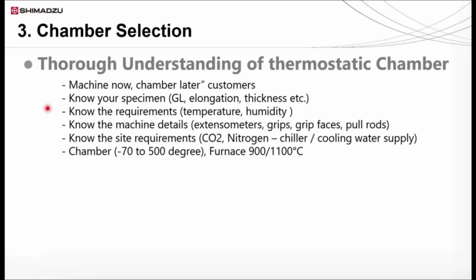First of all, you should have very thorough knowledge about your sample, the gauge length, the elongation requirement, thickness of the sample, the standards you follow, etc. Otherwise, we might end up purchasing a chamber which is not matching our test requirement. Knowledge of test conditions like temperature and humidity is also very important, and this has to be cross-checked with the chamber specification before you buy the chamber. Thorough knowledge of grips, grip faces, pull rods, and extensometer is also very important. A high temperature chamber may require a high temperature extensometer too.